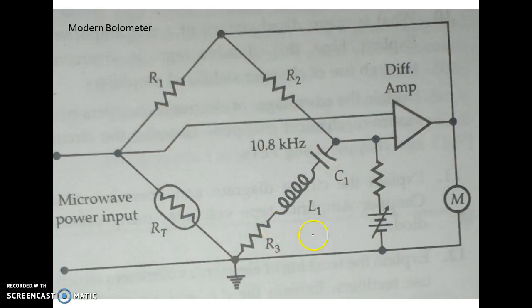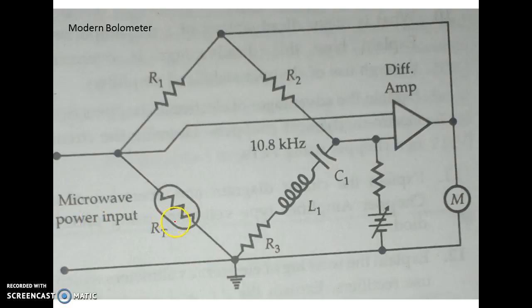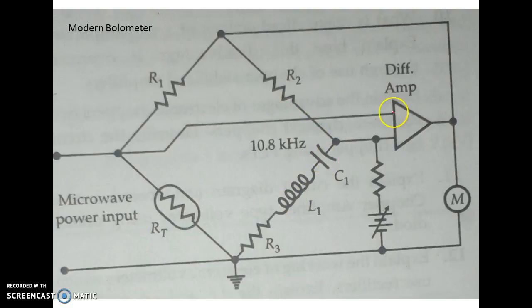Next we have the simplified diagram of the modern bolometer. In addition to the bridge circuit, it has a resonant circuit and a variable DC voltage. When the bridge is imbalanced, it oscillates at a resonant frequency; when balanced, you get the meter reading. When microwave input is given, the bolometer changes its resistance, causing an imbalance in the circuit. A known input voltage is applied and the output of the differential amplifier is measured. When the microwave input is given, there is a change in the differential amplifier output, and the difference between the two values is measured by the meter to give the appropriate power reading.